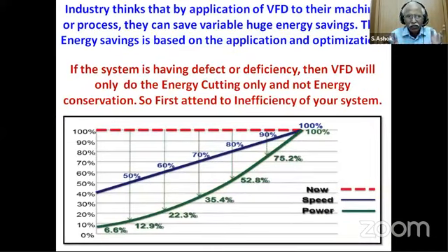Normally, the industry thinks that once they fit a VFD to a blower, they can achieve around 20 to 30%. It is not a question of 20 to 30% being achievable by the VFD alone. The VFD has to follow the best efficiency curve of the given blower. The fan performance curve is a critical parameter that must be made available from the AHU OEM and air conditioning OEMs, AMC service providers, to the users. We need to know where we are operating on the fan performance curve for the given static pressure and flow.